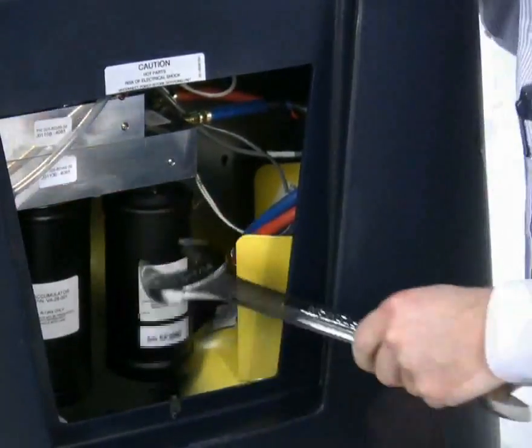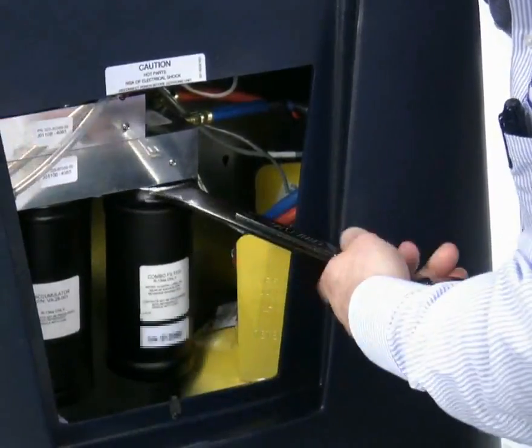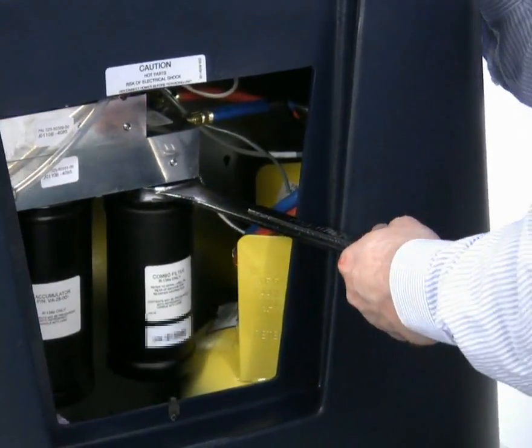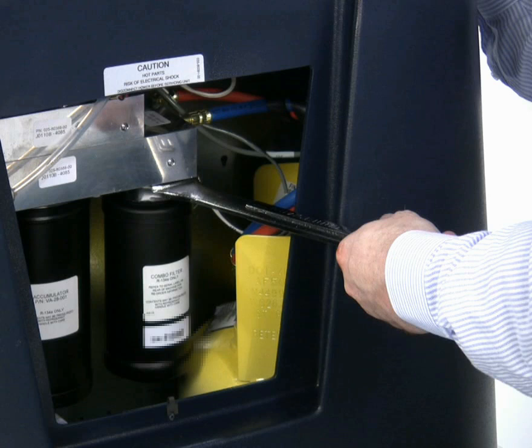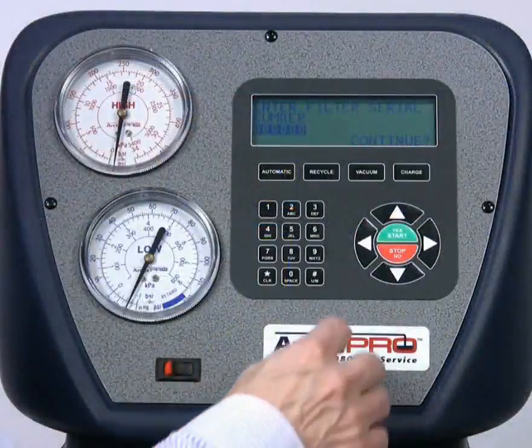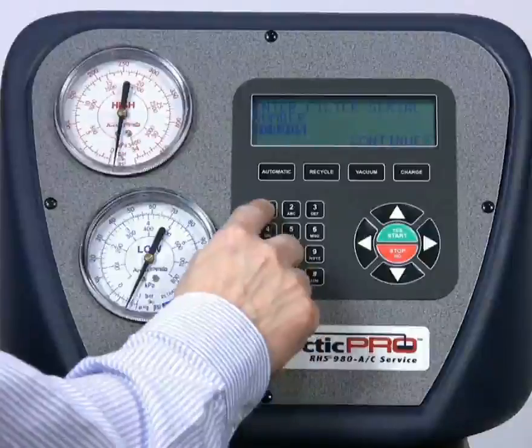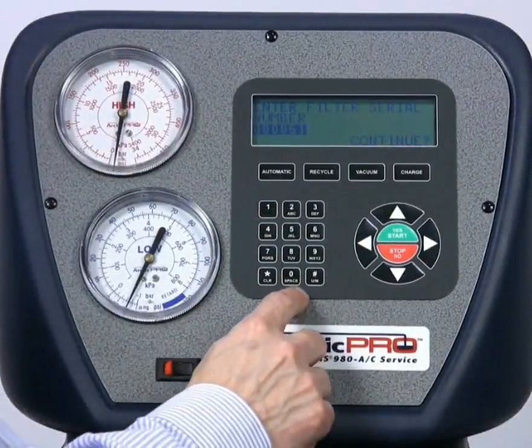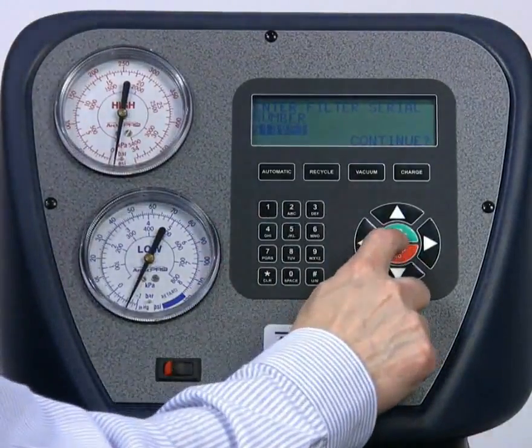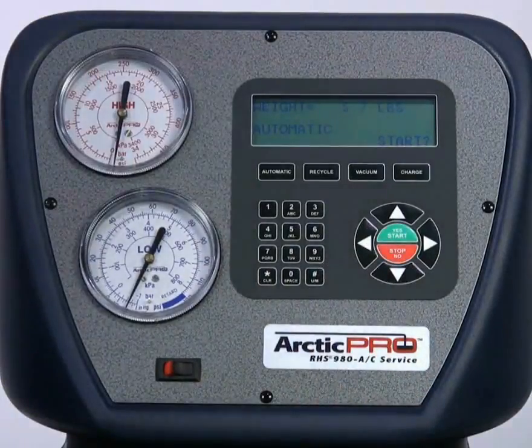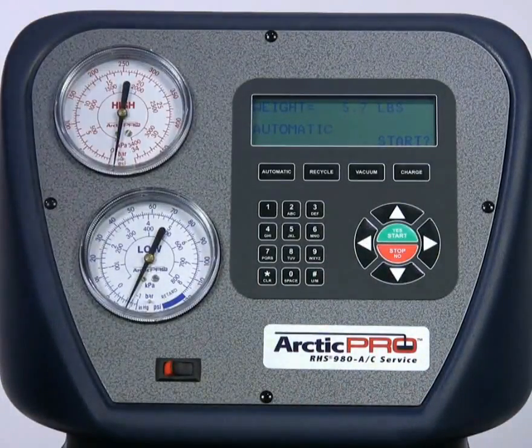Then, apply moderate force by using the open-ended wrench. Caution: do not over-tighten. Do not apply any thread sealer or thread compound to the filter threads before installation into the manifold. Now, enter the new 6-digit combo filter serial number you previously recorded as instructed. Then press the green Yes key. You've just successfully replaced your RHS980 combo filter, allowing you to resume normal RHS980 operation.